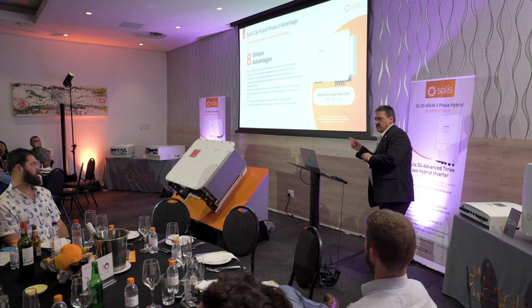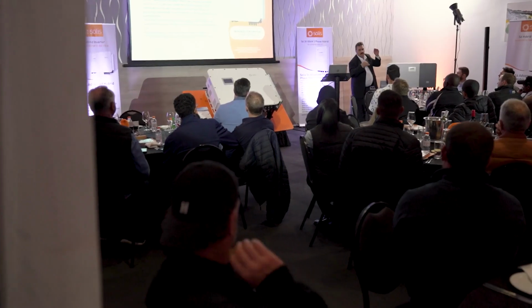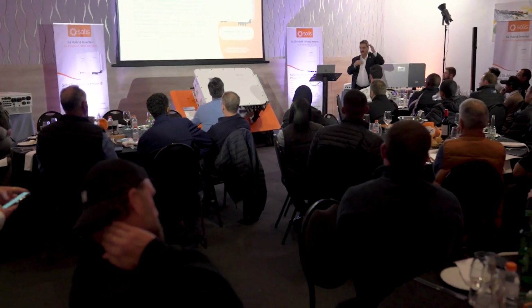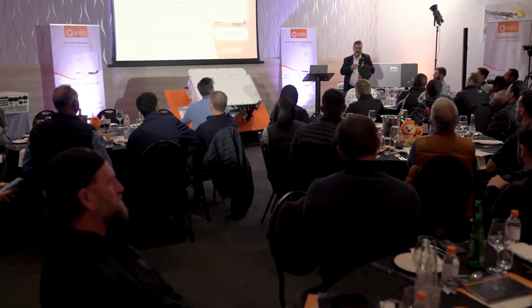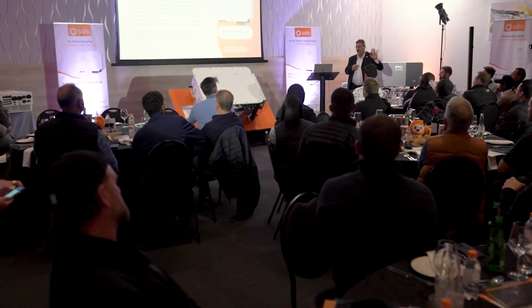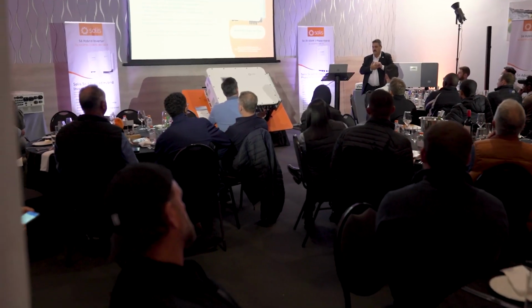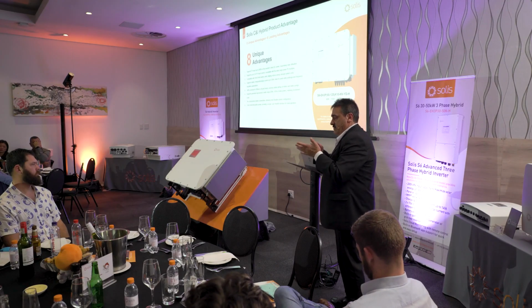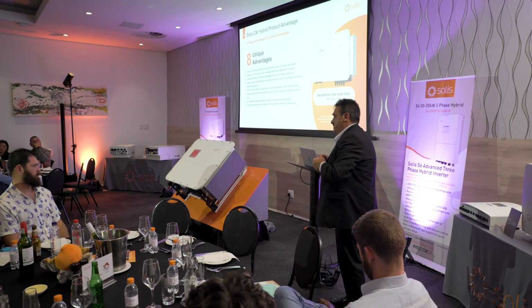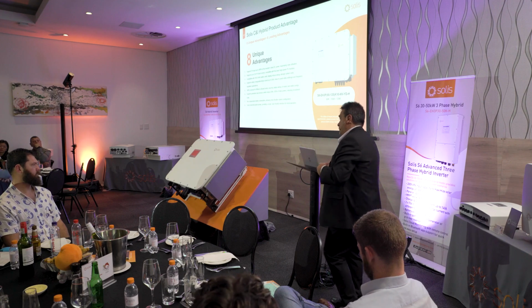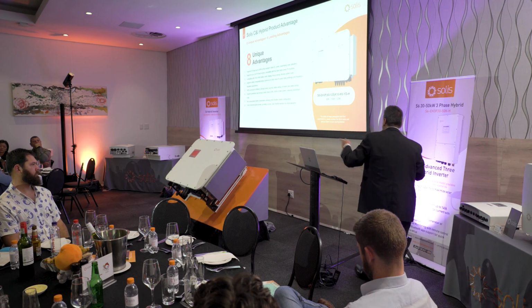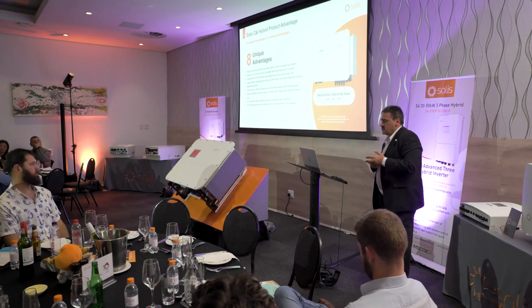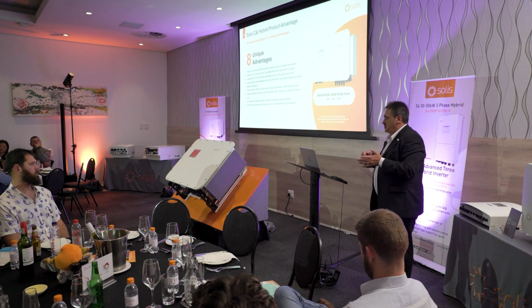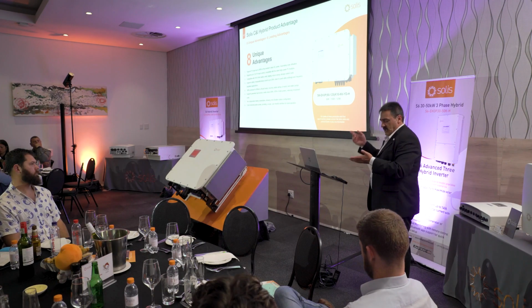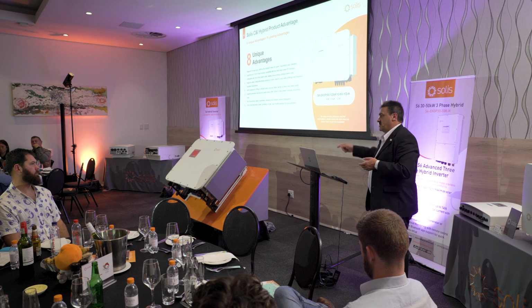We were talking about the generator earlier, coupled to the SOC, stop and start on the SOC. You also have a forced start and stop function within the monitoring platform, so you could say, I need to charge my batteries now - even if it's not connected the normal way, you could force start it because you got a letter from Eskom saying the power's going out.